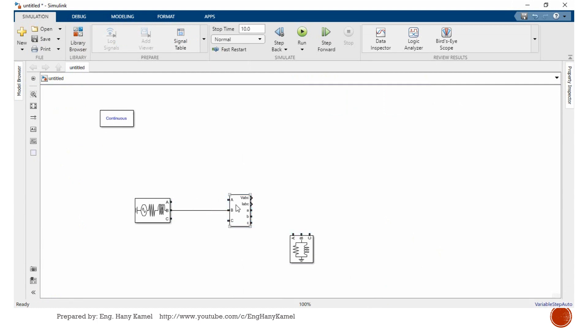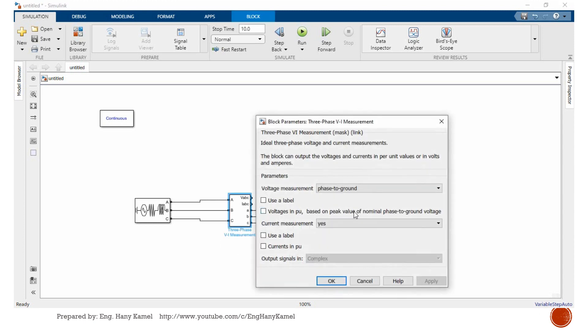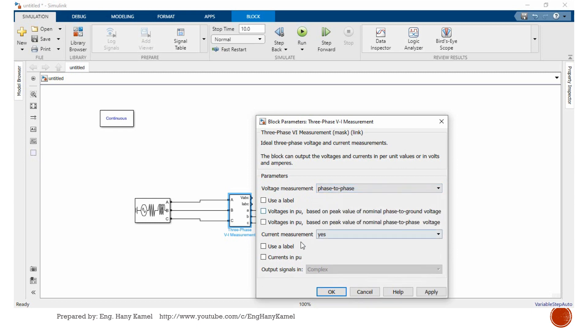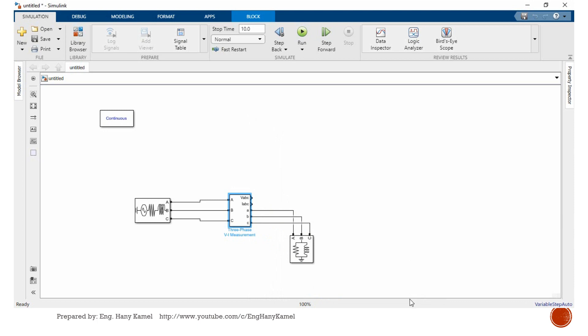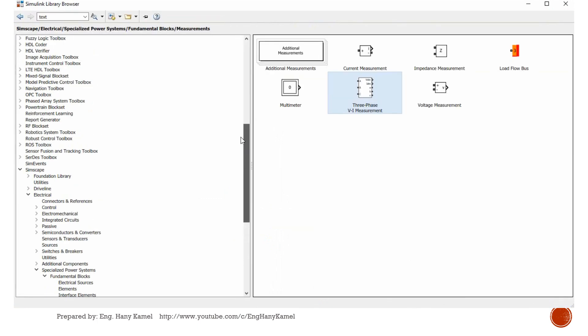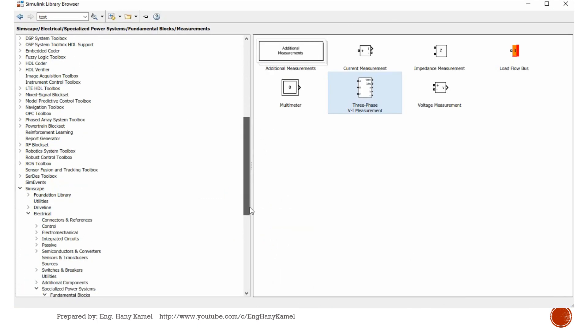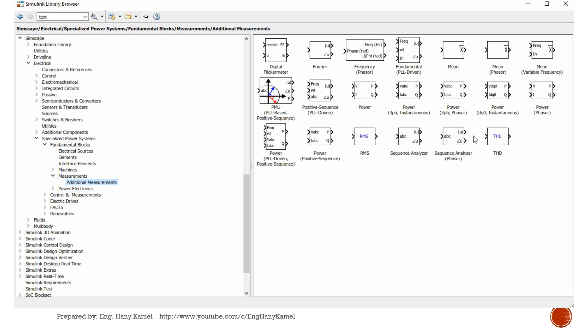We will make some connections. Then we will click three-phase voltage and current measurement. We can select how to measure, phase-to-ground or phase-to-phase. We will select phase-to-phase and current measurement, enable it. We need also to read some RMS values, not only instantaneous values. We'll go to additional measurement. For now, we'll select RMS.